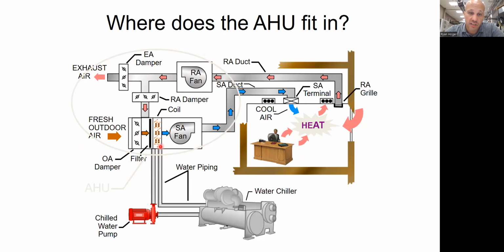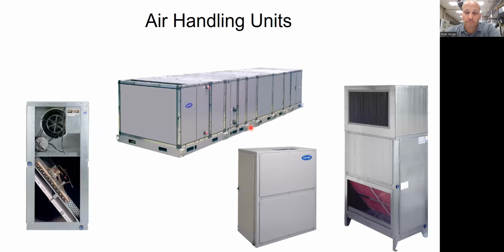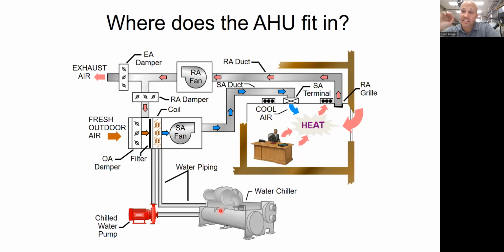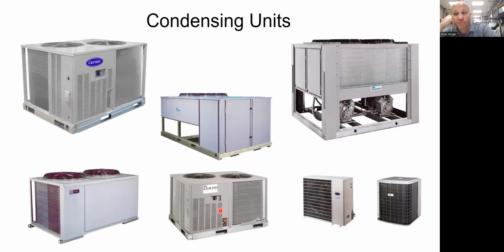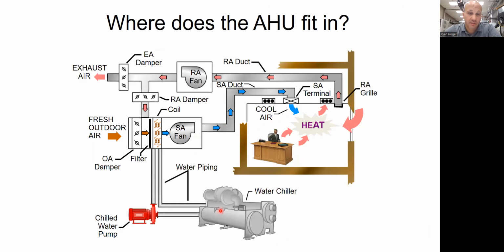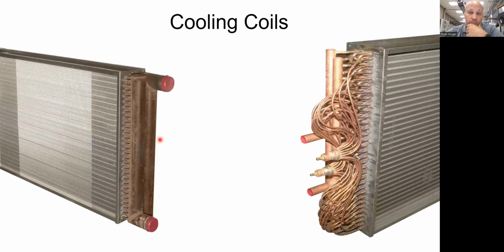And then we take that into your heating and cooling coils, into the supply fan, and bring it into the space. This cooling coil right here could be fed with a chiller, like it is in this case. A chiller makes cold water and sends it over here. Or it could be one of those split condensing units we talked about over here. If it's a chiller, that's going to be a different solution for heat pump versions, and we'll talk about that in Module 5. So if it's going to be a DX system, meaning it's got one of these units on the roof, piped over to this guy, right? That's what we're talking about today, and what we can do to replace that with a heat pump version.